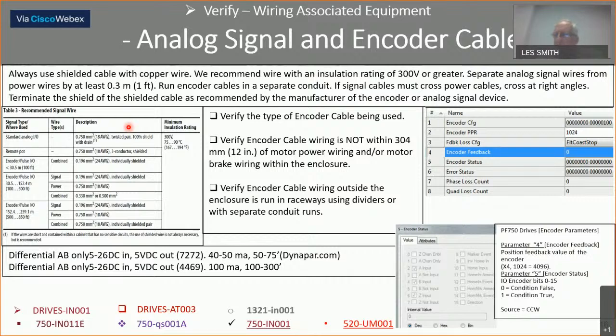I've had runs where we had 300-foot runs and we could run up to 40 hertz, 45 hertz, and then we get errors if we tried to go faster, and the capacitance in the wire would draw the power away from the encoder pulses. It would pull it, capacitively couple it. So you had to have the right cable there.